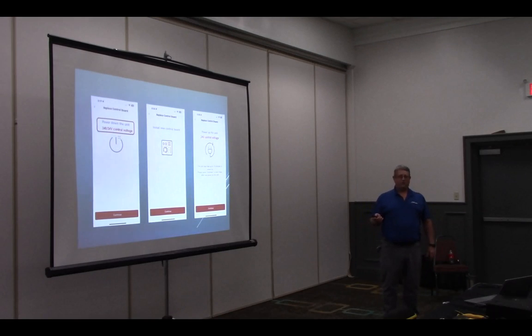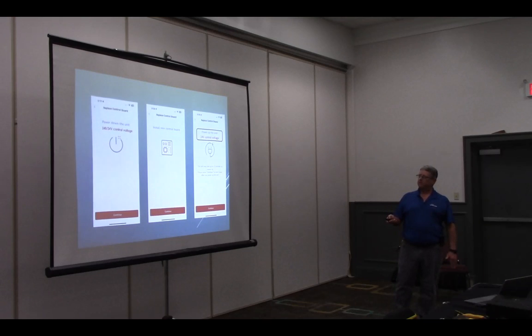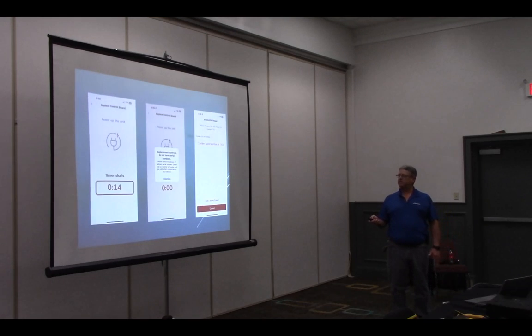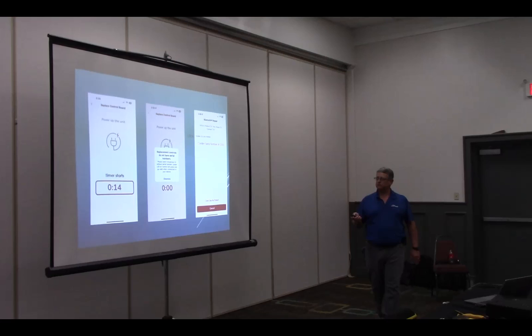If you have a bad control board, change the board. But if we're just updating software, we're going to pretend we changed the board, right? Change the control board, power everything back up, hit continue. You're going to start a 15-second timer. When that timer ends, you're going to get this message: Replacement controls do not have serial numbers. Hit dismiss. Okay? Because if you put a new board in, it's blank, right? It doesn't have any serial numbers in it.